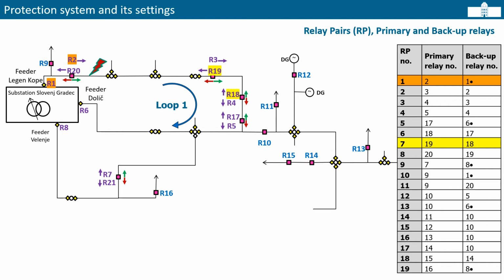Here we have a presentation of our protection system. It consists of relay pairs. Each relay pair includes a primary and a backup relay. For the fault marked here between the relays R2 and R3, the primary relay pair consists of the relays number 2 and number 1. So the relay R2 is the primary and R1 is the backup relay. If we observe this fault from the other direction, then the primary relay is R19, and the backup relay is R18. They build the relay pair number 7.